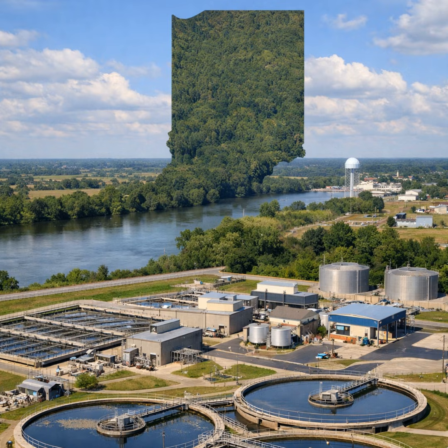Supernatant. Supernatant is liquid removed from settled sludge. Supernatant commonly refers to the liquid between the sludge on the bottom and the scum on the surface of an anaerobic digester. This liquid is usually returned to the influent wet well or to the primary clarifier.